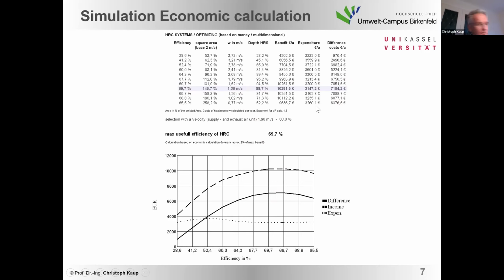That means that we have a much higher amount of income compared to the 1D optimization. If we change only the depth of the heat exchanger, then we will see that the maximum would be 6,500 euros, for example. Yeah, so that means that we have the possibility to increase our income by a 3D optimization, and that is the best optimum of all kinds of optimums.